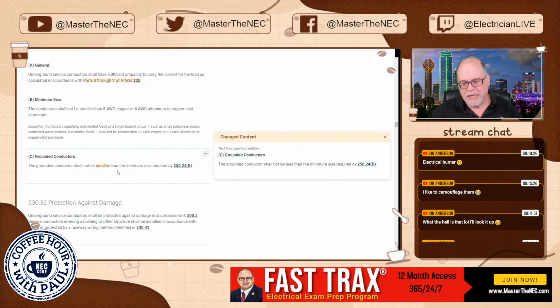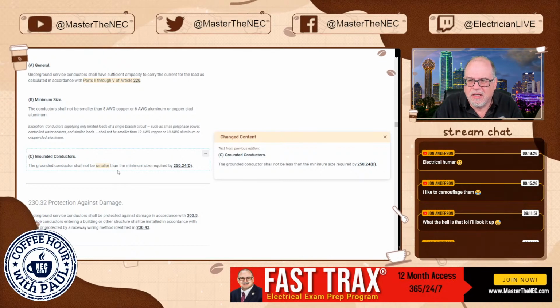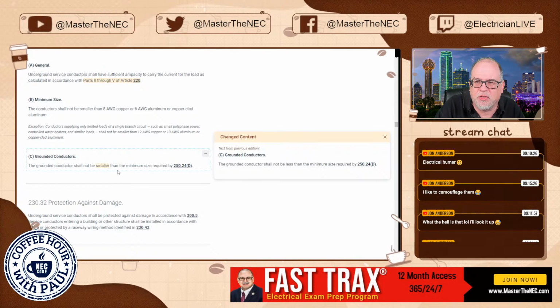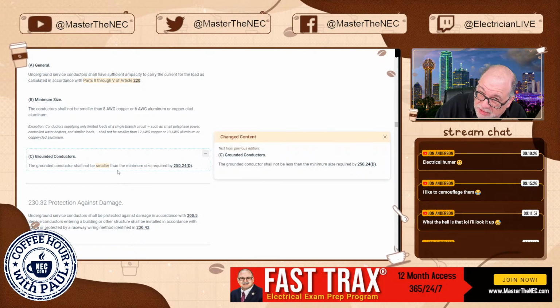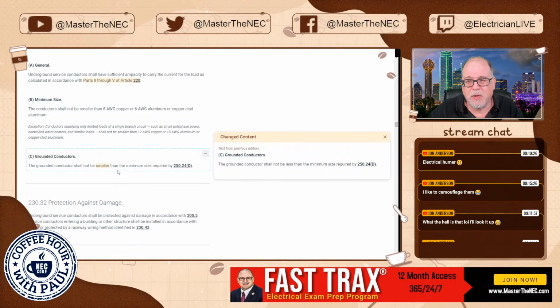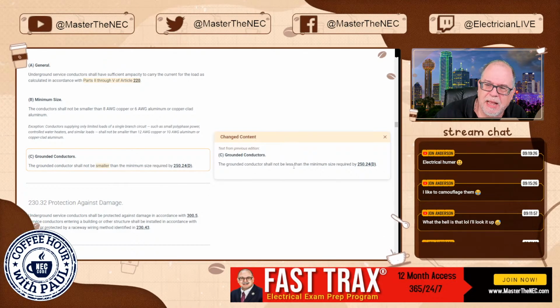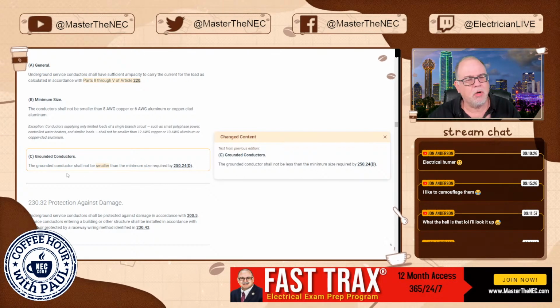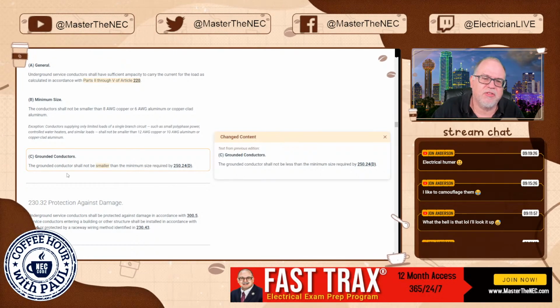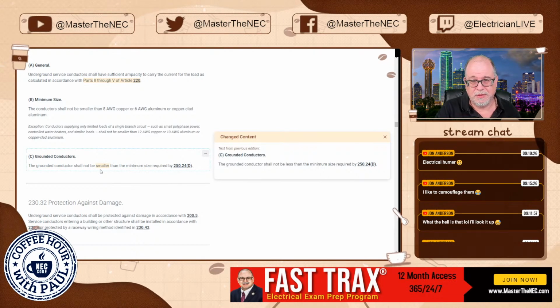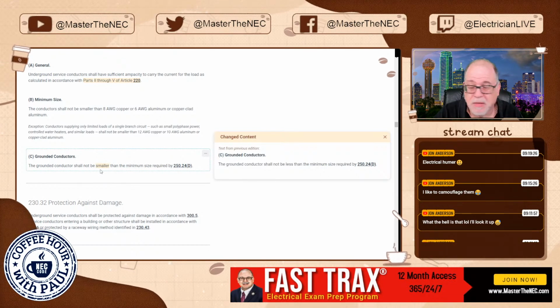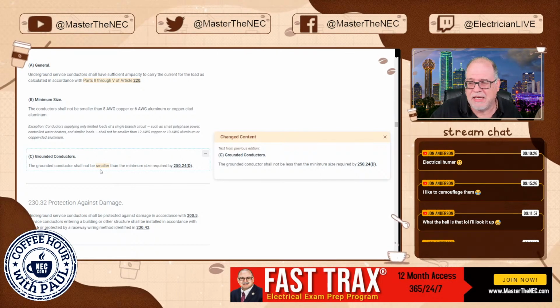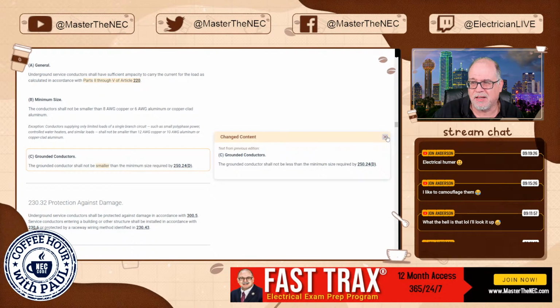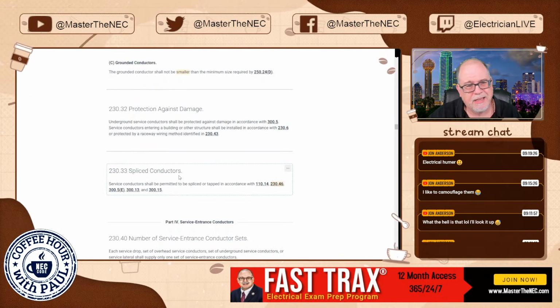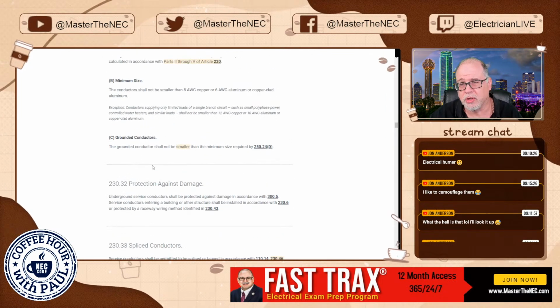When we're sizing, we can't have a grounded conductor that is less than the minimum size in 250.24(D). Now that's going to ultimately end up sending you to 250.102(C), but here's what it said previously. It says the grounded conductor shall not be less than the minimum size required in 250.24(D). Well, the code panel said, no, what are we really saying here? It says the grounded conductor shall not be smaller than the minimum size required in 250.24(D). Look, it may seem like, why make this change? Well, again, it's an effort to make it a little clearer on what it's trying to say and get rid of the ambiguous terms and things that people could argue out of the code, right?